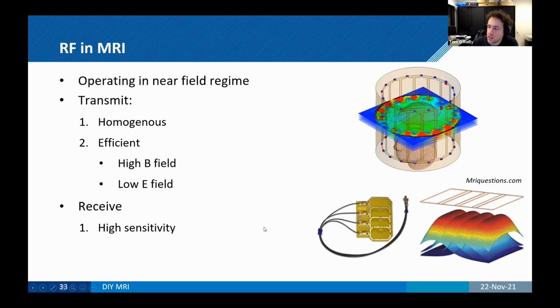And then on the receive side, you don't really care about homogeneity. What you really want is to be as efficient as possible. And the way to get efficient at high field is to use coil arrays that can be placed as close to the body as possible.